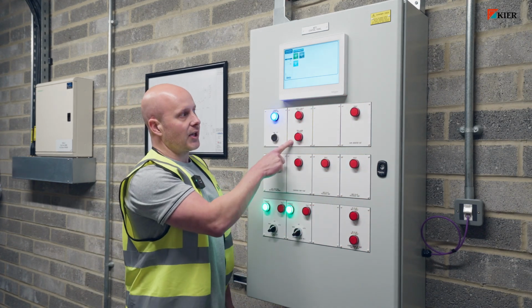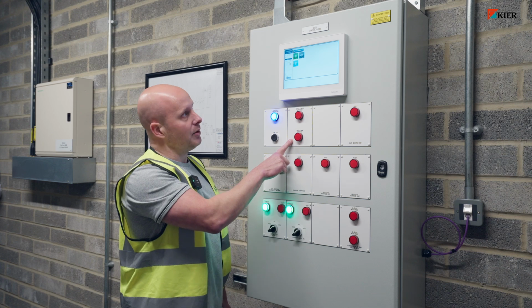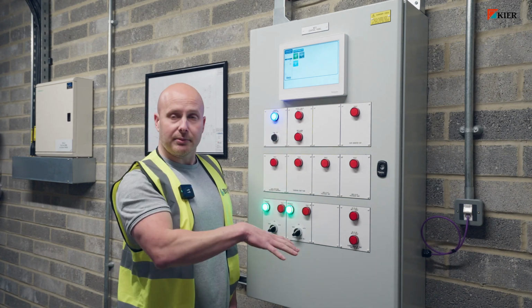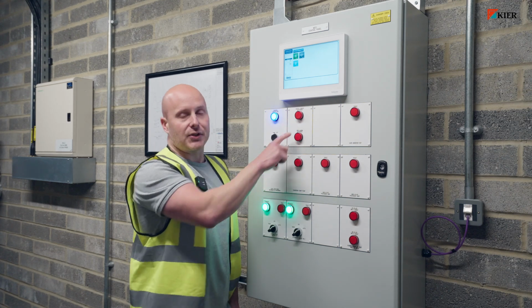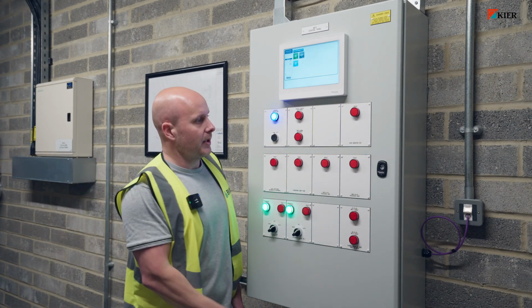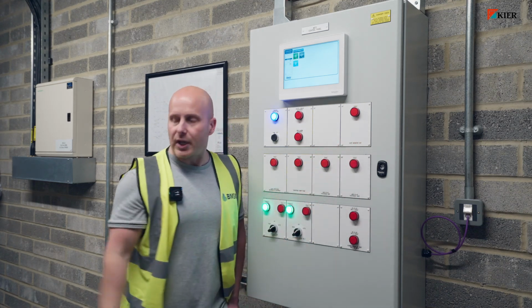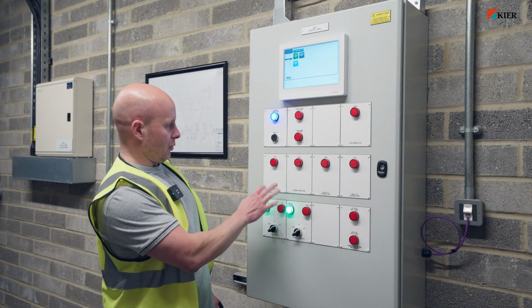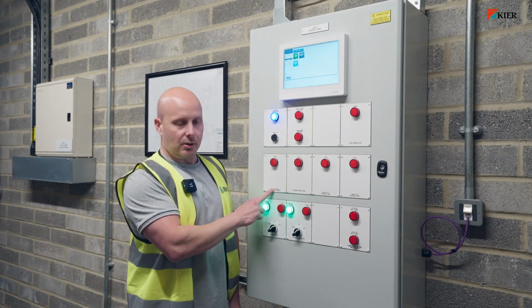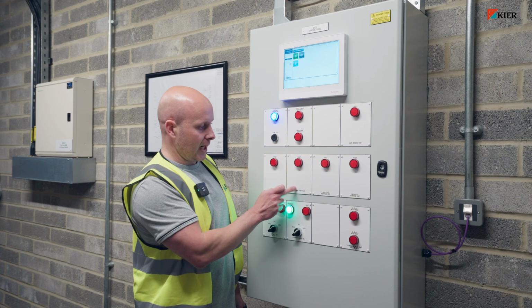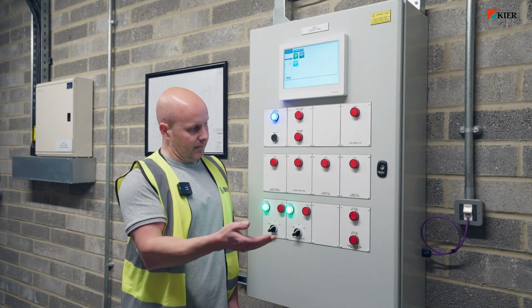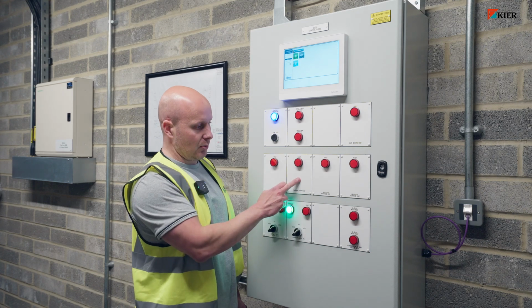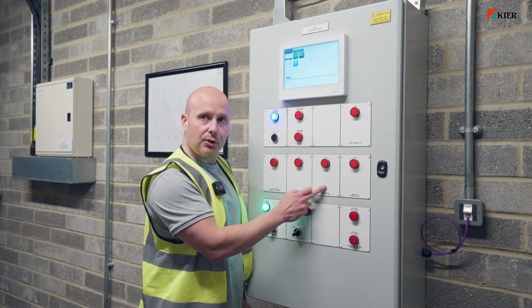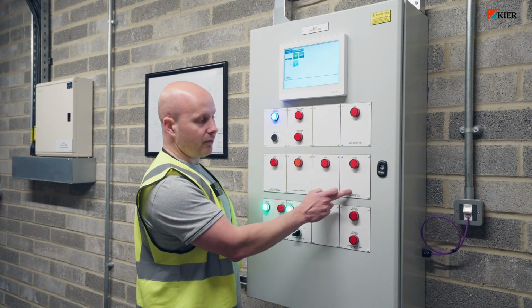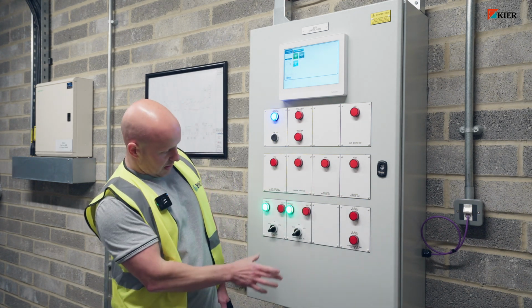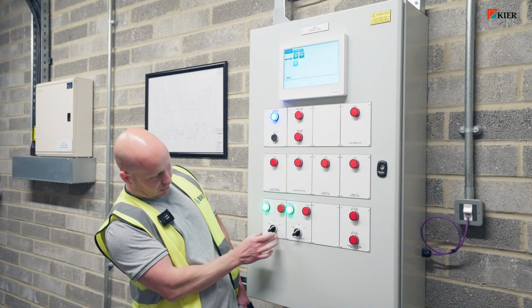Okay, this is your safety circuits. Either of these activate and come on, any plant within this will shut down. So that's your fire alarm and your safety circuit. Your safety circuit is a push button in the corner. We have a fault here for the Cat 5 booster set, which is the water tank just there. We also have a fault for the leak detection. So any leaks detected, this will come on. Tank room sump pump, which is next door. Again, if that goes into alarm and the water level raises too high, this light will come on. We have a fault for the air handling unit, which is up on the roof. We have a fault for the heat recovery unit, which is just a couple of doors down. Then we have here a switch for the extract fans.